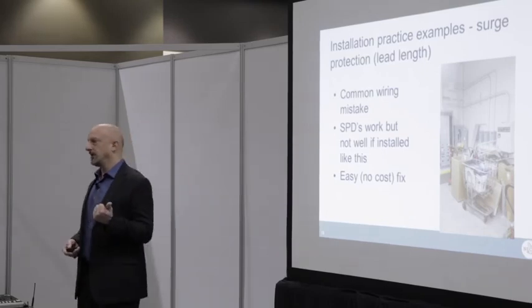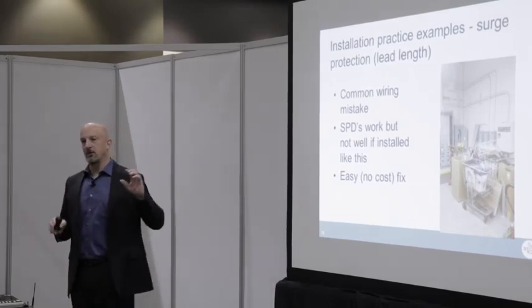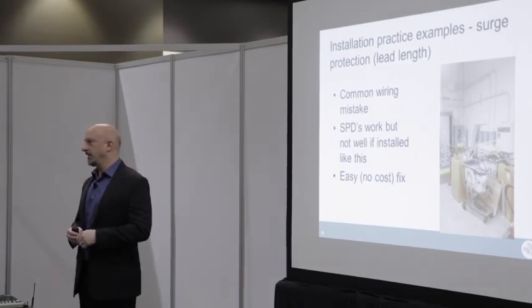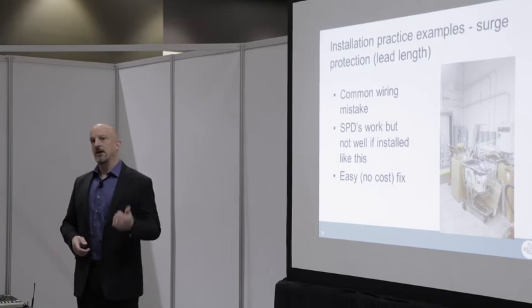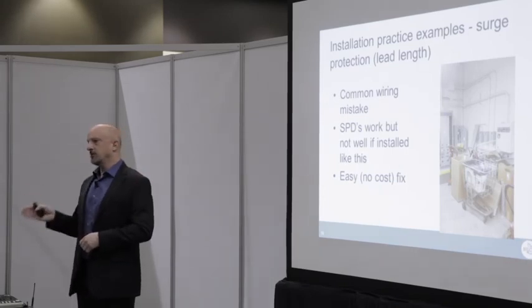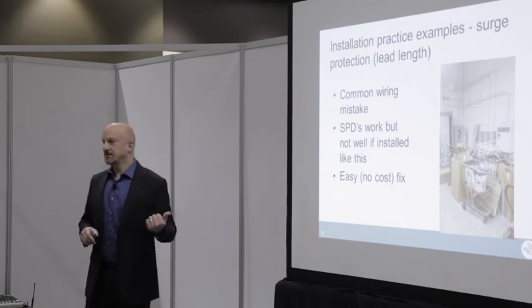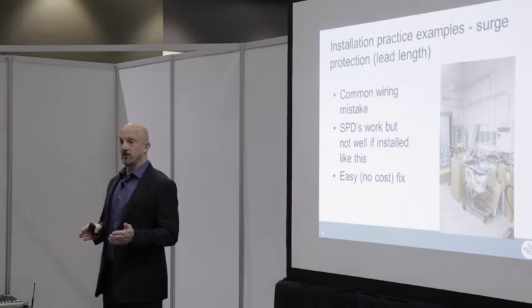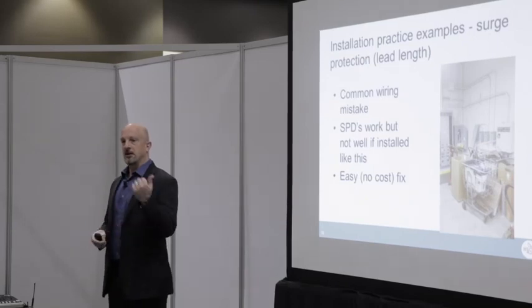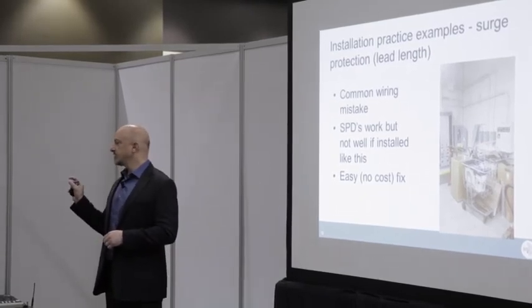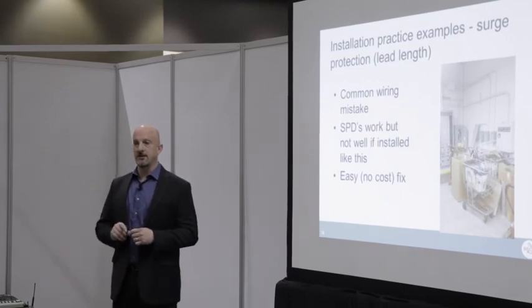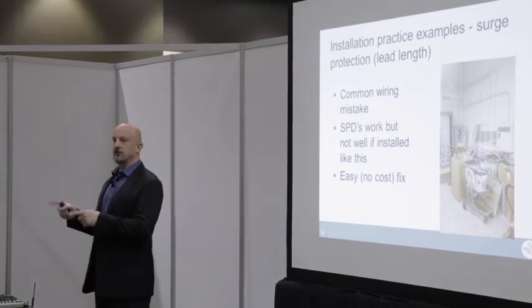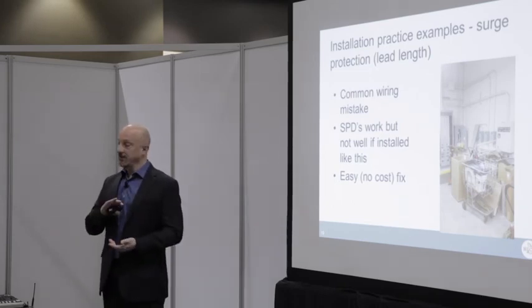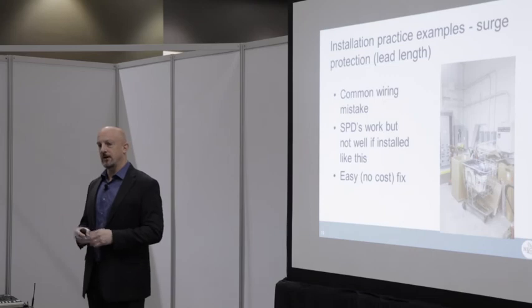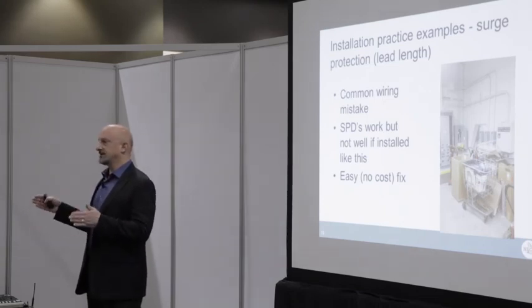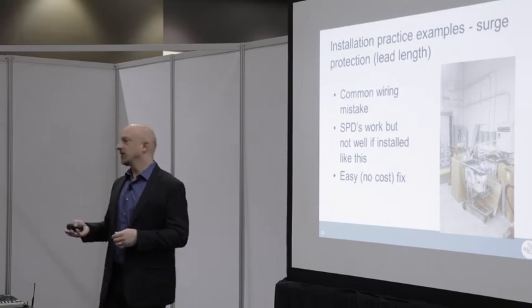In the power quality lab we show one installed on the bus inside the panel board, one that's 12 inches away, and one that's 3 feet away—good, better, best. The one inside the panel is actually less than 400 volts because it's under 6 inches. The one 12 inches away: for every inch of lead length you get about 20 volts of let-through, so it's 6 inches too long, 120 volts on top of the 400, making 520. The one 3 feet away is 30 inches too long, 30 times 20 is 600 volts on top of 400, so it's over 1,000 volts.